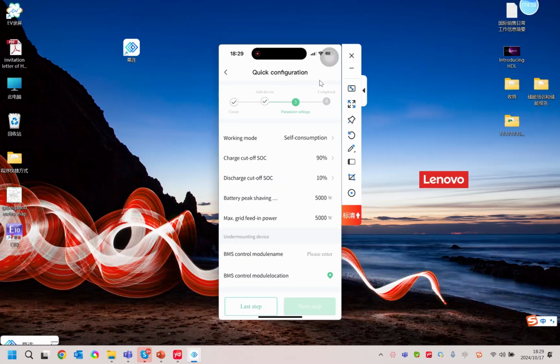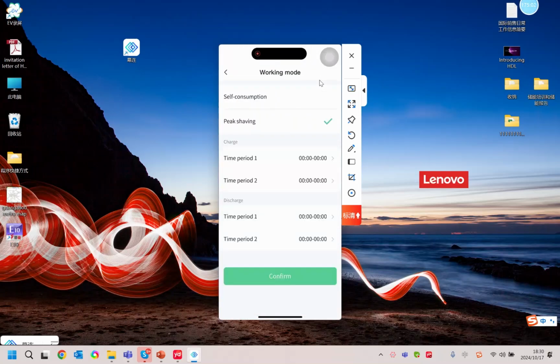This one is for battery peak shaving power. This parameter is related to - actually there is a small mistake here, because this parameter you only need to set when your working mode is peak shaving. When we choose peak shaving, you can set 2 time periods of charge time, because if you choose peak shaving, it means you want to charge your battery in valley price time and discharge it in peak time. Here you have 2 time periods to set.